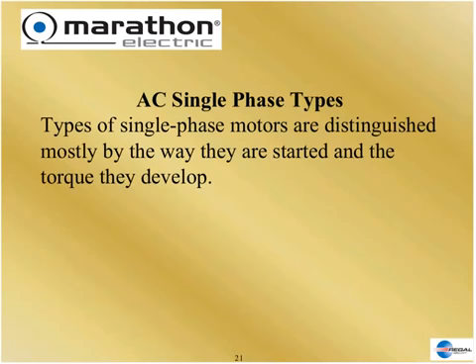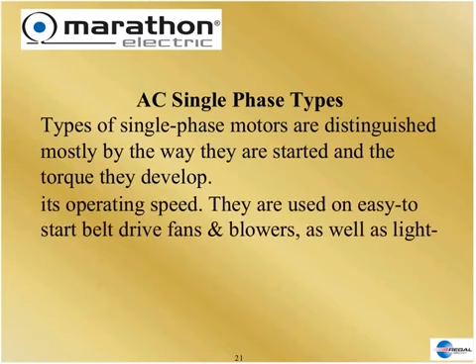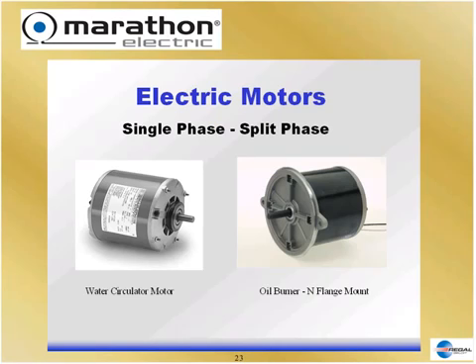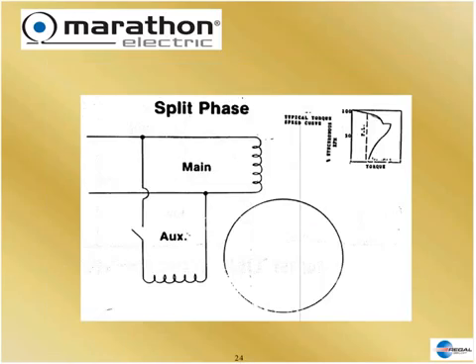Most single-phase motors are named for the way they are started and how much torque they produce. One of the most common is the split-phase motor. Split-phase motors have moderate starting torque, and the switch is involved in taking the start winding out of the circuit. They are usually used for variable torque loads — fans and blowers that are easy to start, so you don't need a lot of starting torque. Split-phase motors are used in furnaces, air conditioners, water circulators, light pumping applications, fans, and blowers.